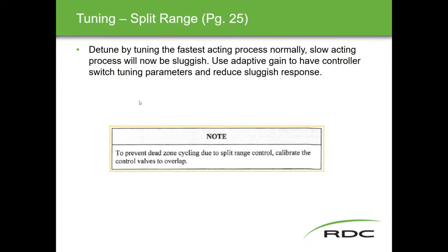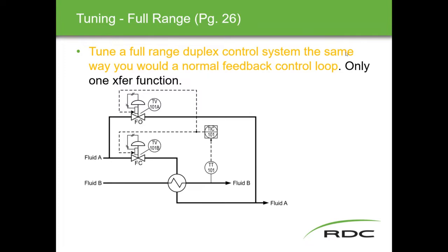An important note: to prevent dead zone cycling in split range control, calibrate the valves to overlap. In the examples shown, one valve covers 0–50% and the other covers 50–100%, so near the 50% boundary both valves are ambiguous. The fix is to have them overlap slightly — for example, 0–52% and 48–100% — to avoid cycling in that dead zone.